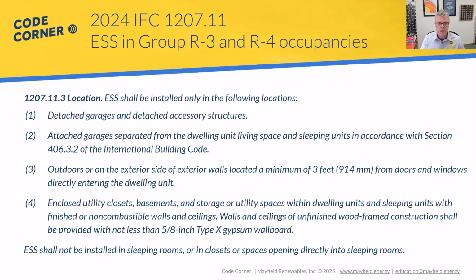Now, what you see there, it says walls and ceilings of this unfinished wood frame construction. So it's not really telling us, is that just directly behind the energy storage? Is that the entire room? The prevailing interpretation on this is that it's the location, the room in which those batteries or the ESS is being installed. So if you're putting it inside an unfinished garage, be prepared to be finishing that garage with that gypsum board.